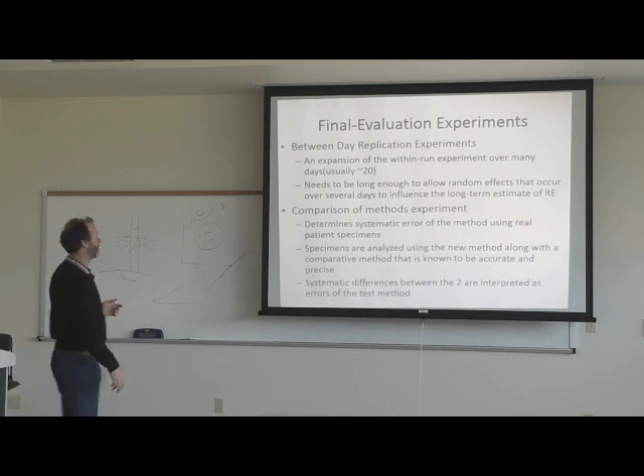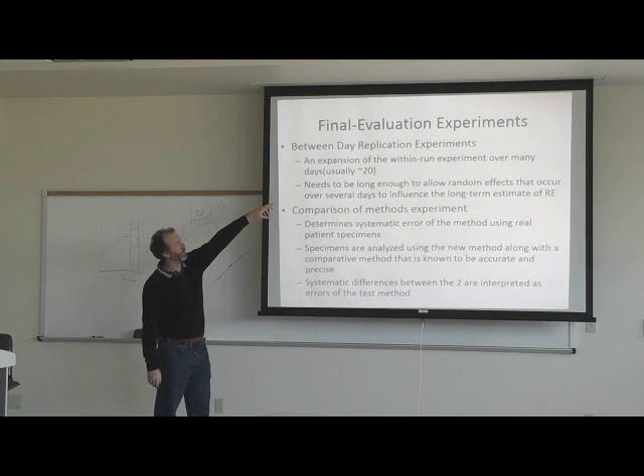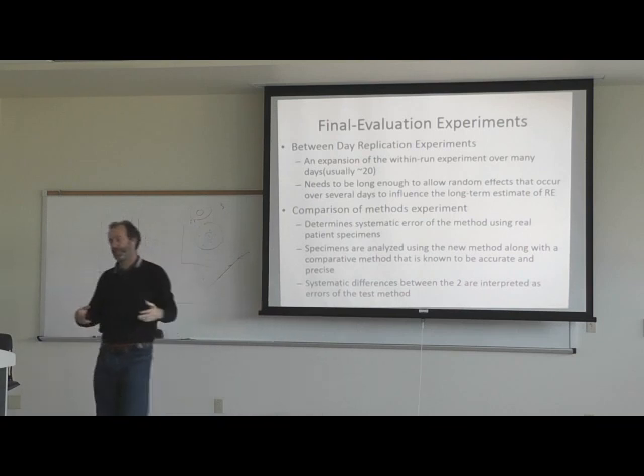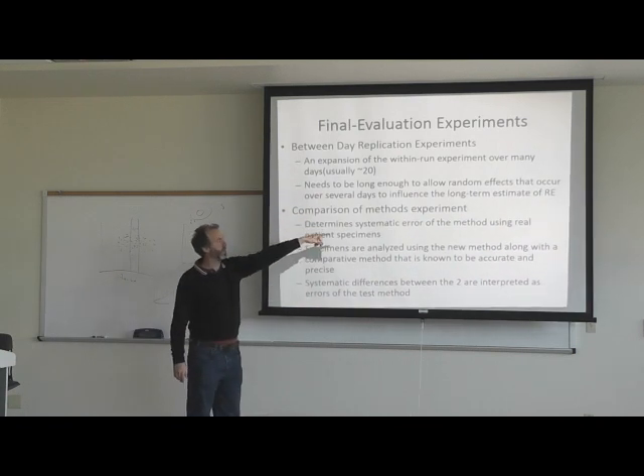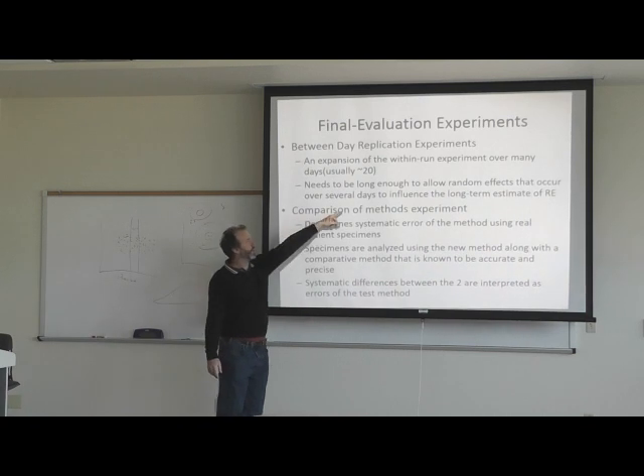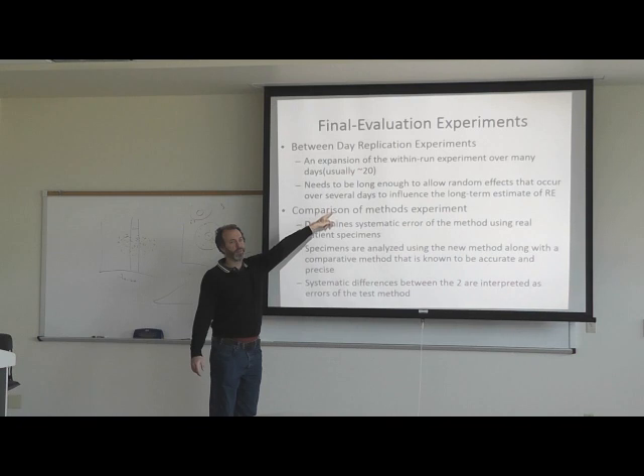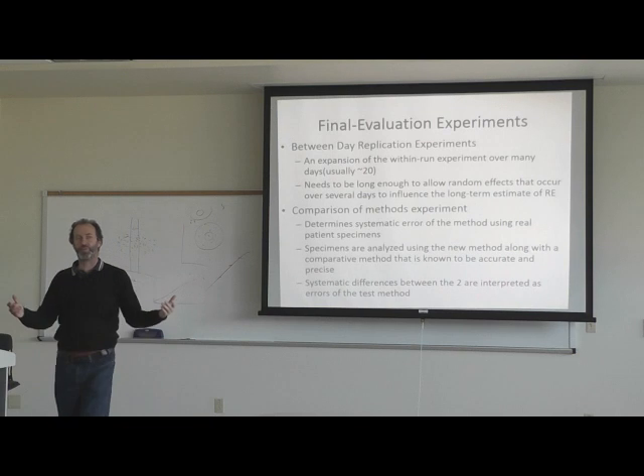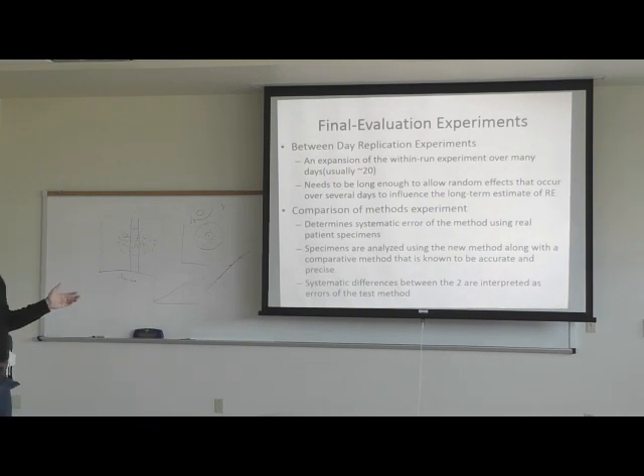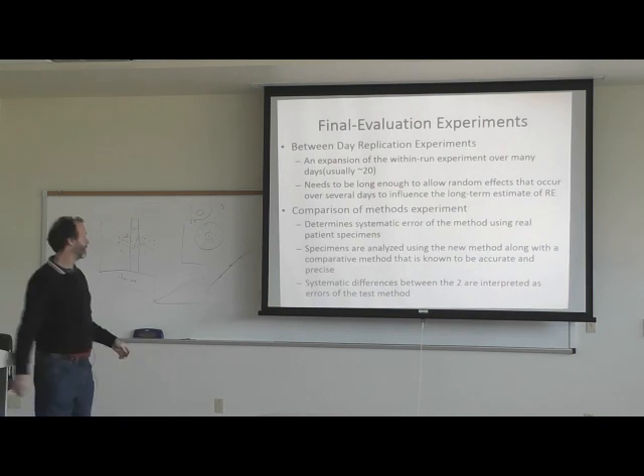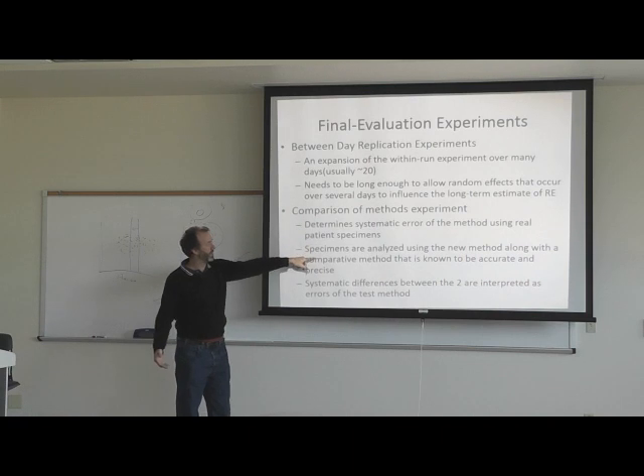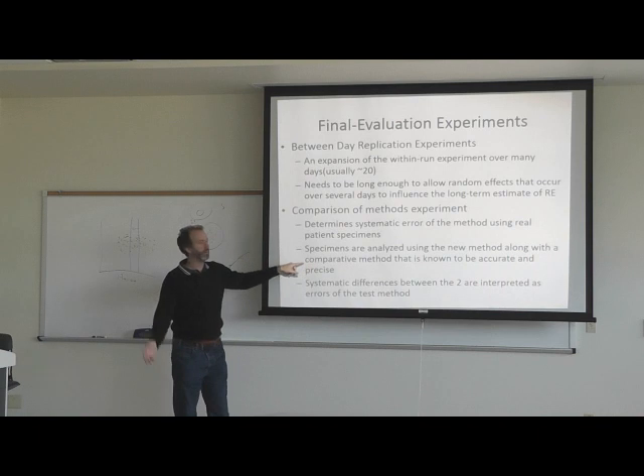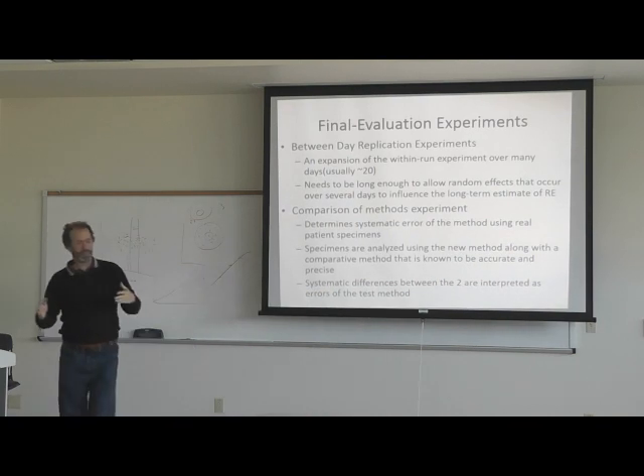Final evaluation experiments: between-day replication experiments are an expansion of within-run experiments over many days, usually at least 20. They need to be long enough for random effects that occur over several days to influence the long-term estimate of random error. You'll want different lots of materials and different users. The comparison of methods experiment helps determine the systematic error using real patient specimens analyzed in parallel with an established accurate and precise method. Systematic differences between the two are interpreted as errors of the new test method.